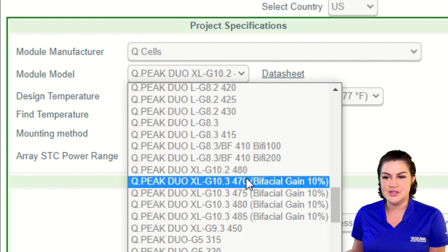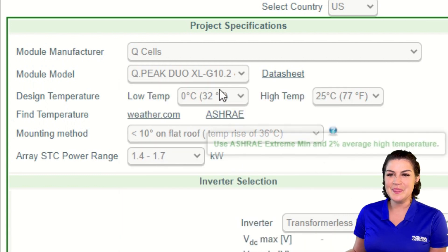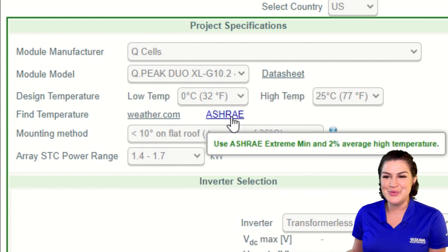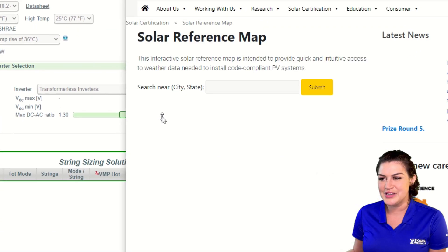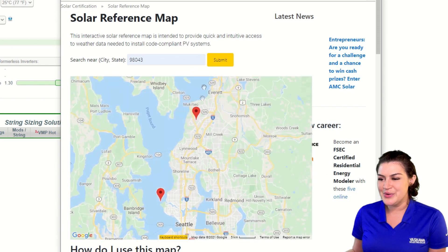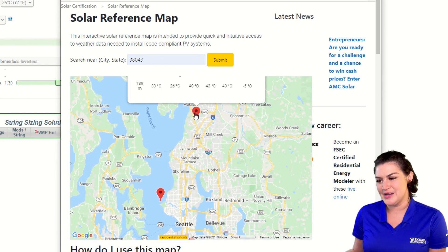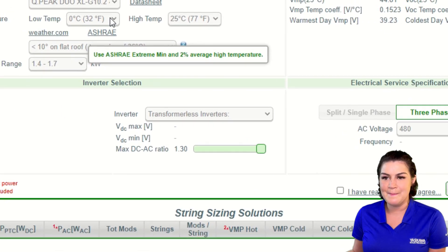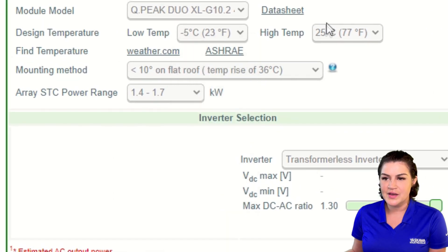Otherwise, we'll just default to 10%. The next step is design temperature. We are going to click the ASHRAE link, and we can just put in our zip code and then select a weather station near the site. I'm going to select this one and note 26°C and negative 5°C — so negative five and twenty-six.